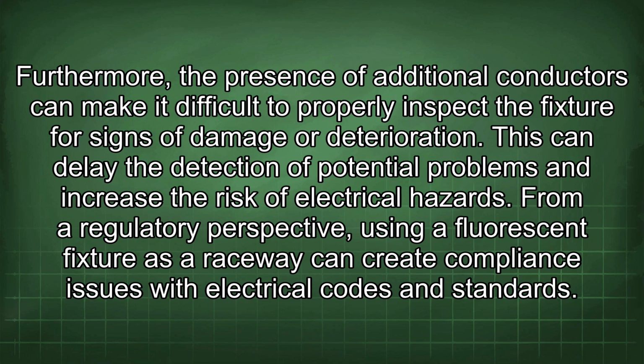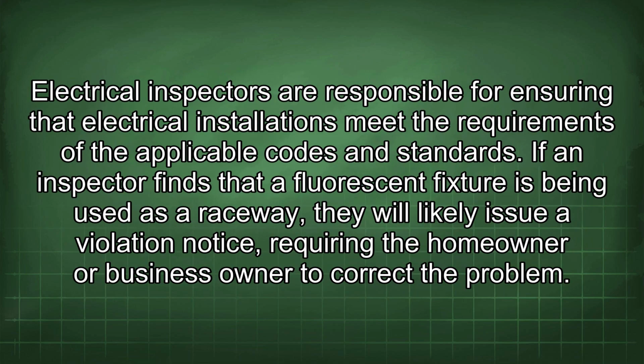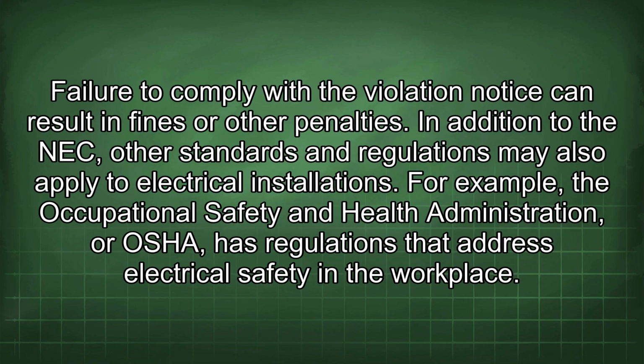From a regulatory perspective, using a fluorescent fixture as a raceway can create compliance issues with electrical codes and standards. Electrical inspectors are responsible for ensuring that electrical installations meet the requirements of the applicable codes and standards. If an inspector finds that a fluorescent fixture is being used as a raceway, they will likely issue a violation notice requiring the homeowner or business owner to correct the problem. Failure to comply with the violation notice can result in fines or other penalties.